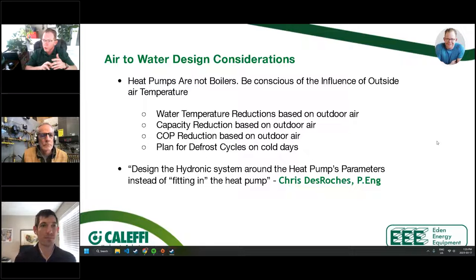The other really important thing that comes into play is the COP will be impacted not just by the outdoor air temperature, but also by our design. So we can't control the outdoor air temperature, but we can control the design. And again, this is where Bob and Max and I are really hitting on this point, that we want to make sure we design the systems to maximize that coefficient of performance for that equipment. You don't want to put a brand new air-to-water heat pump in, or any hydronic heat pump, and inadvertently give them an electric furnace. We want to make sure we design this properly, that we are maximizing the efficiency.